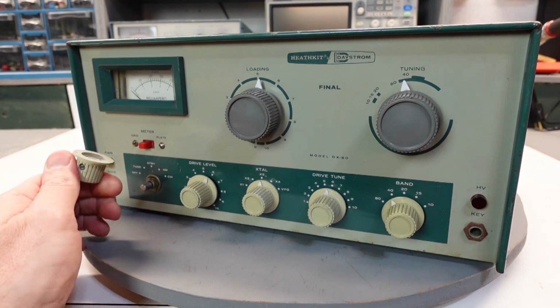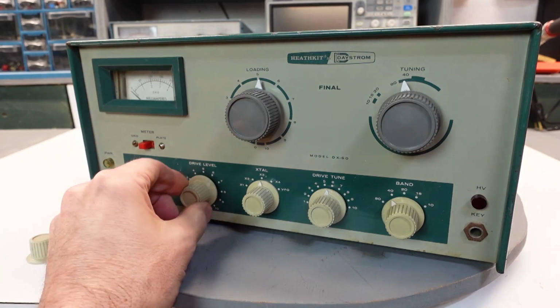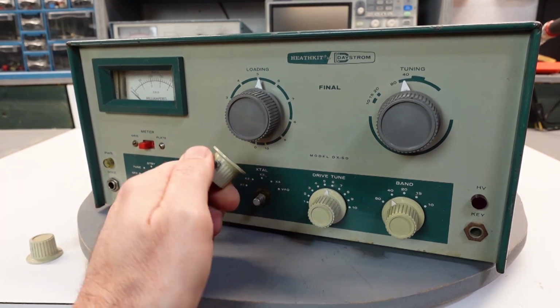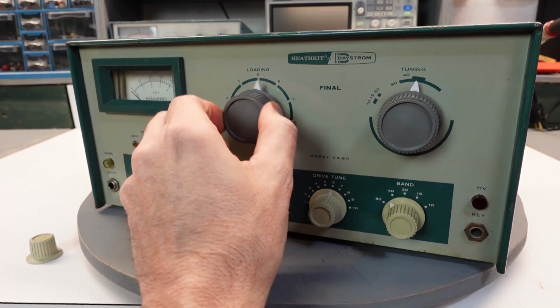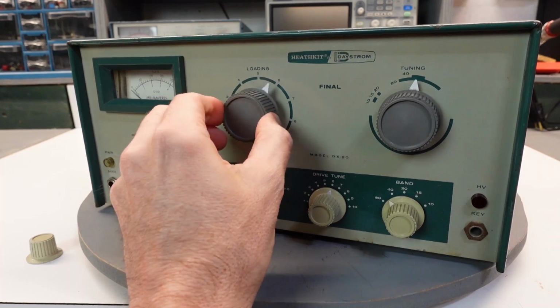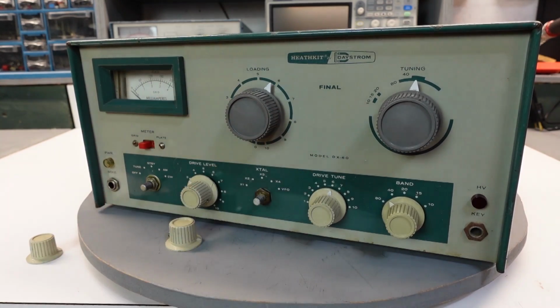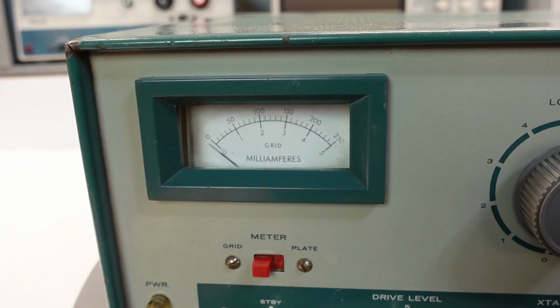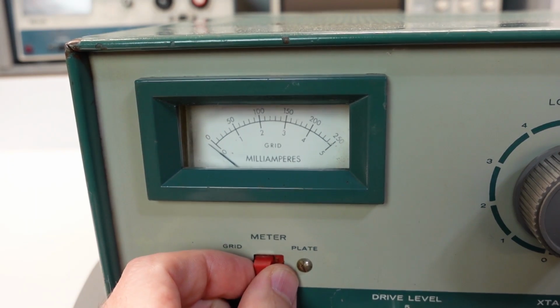The front panel is in good shape. The knobs, however, not so much—most are split and cannot be tightened down anymore. And something is definitely broken on the load control. Visually, the meter looks fine, but I'll definitely have to check it functionally.